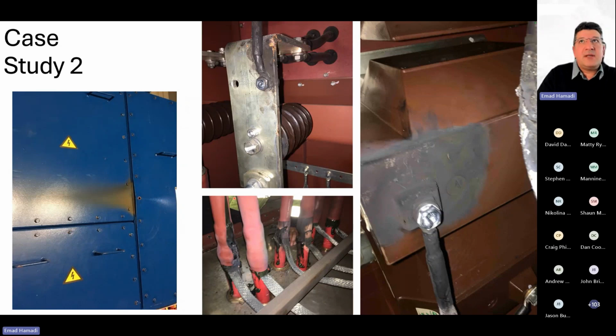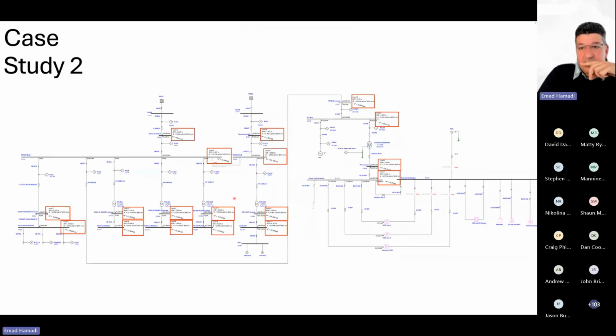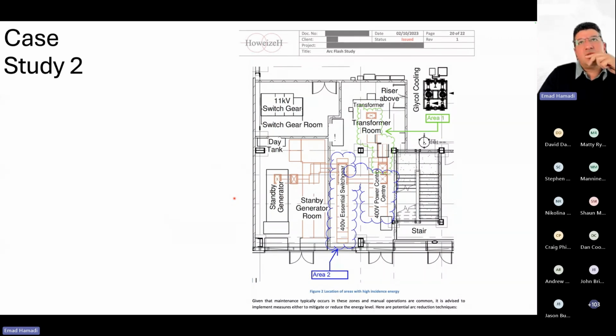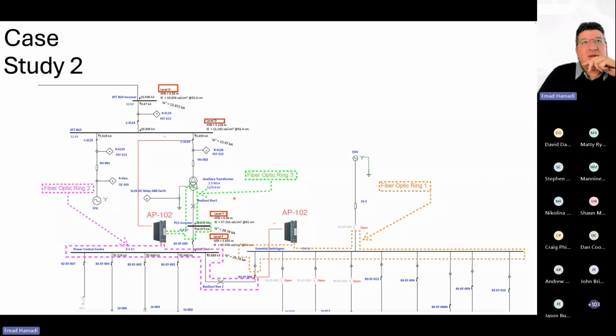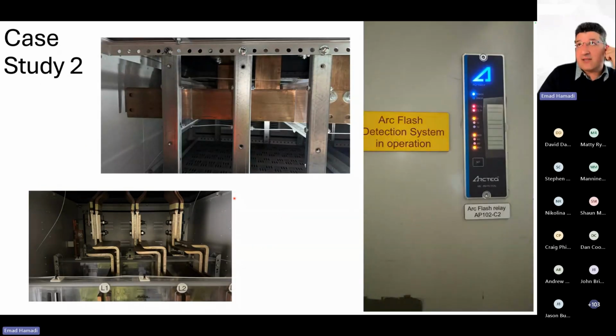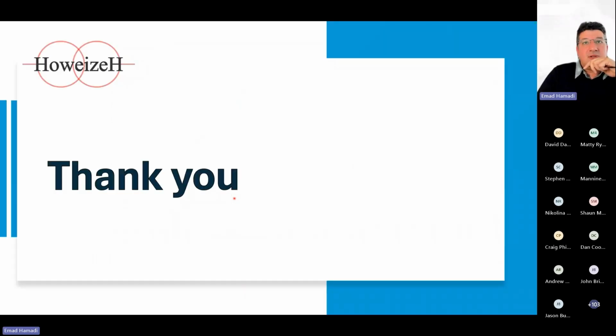This is another case study, actually. This happened at one of the sites. An arc flash happened. Following the incident, the management was advised to install extensive arc flash protection and a partial discharge system. However, they decided to conduct an arc flash study first to better understand. The study revealed that only specific areas were vulnerable to arc flash hazards, and we managed to reduce that with a very cost-efficient approach by changing the settings and eventually installing only 2 arc flash relays, and we ended up with a safe and sound system at the end of the day. So this is almost all about the arc flash study.